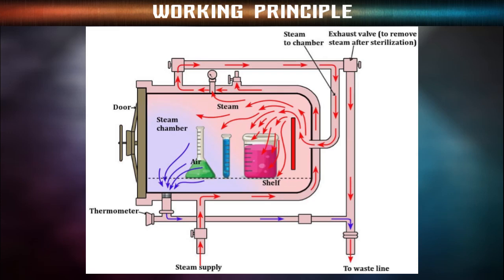Once the sterilization phase is completed, which depends on the level of contamination of the material inside, the pressure is released from the inside of the chamber through the whistle. The pressure inside the chamber is then restored back to the ambient pressure while the components inside remain hot for some time. Procedure or operating of the autoclave. In general, an autoclave is run at a temperature of 121 degrees Celsius for at least 30 minutes by using saturated steam under at least 15 psi pressure.